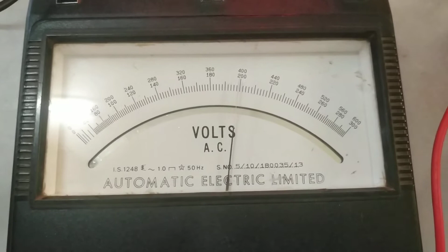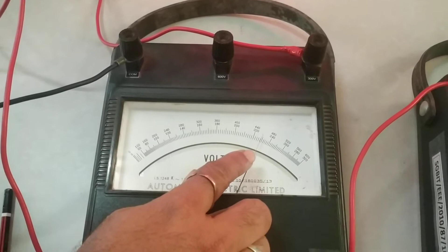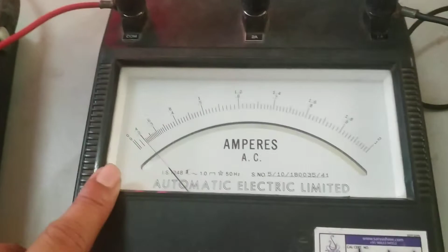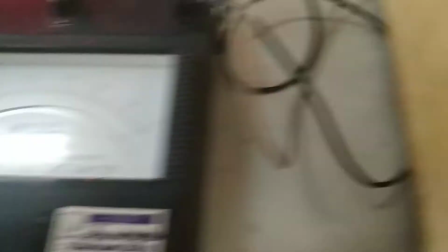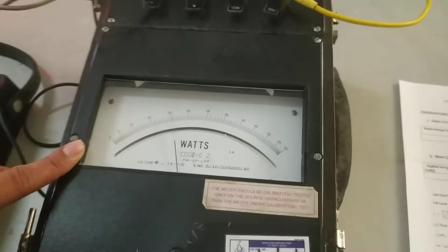As we know, the rated voltage of the transformer is 230. Here we are using a 0 to 300 range. This is 220, which means we need to read the lower scale. Now it is 230, right? So we apply 230 volts to the primary circuit of the transformer. After applying 230, we need to see the ammeter reading as well as the wattmeter reading. Those readings should be taken and put in the tabular column.